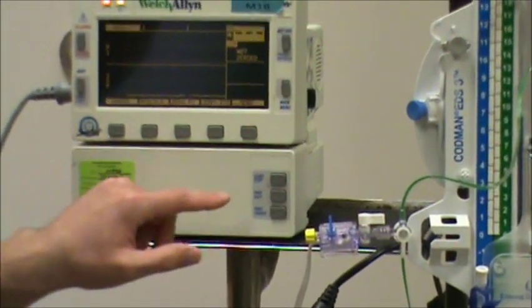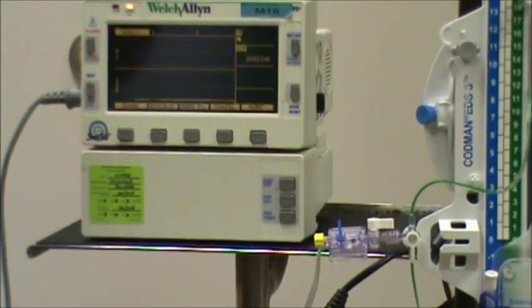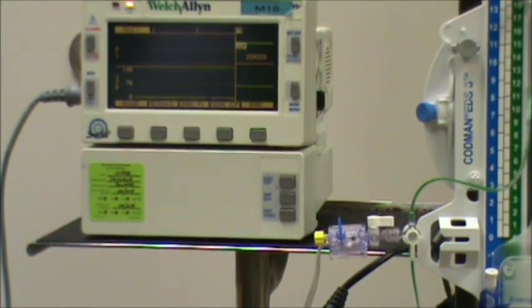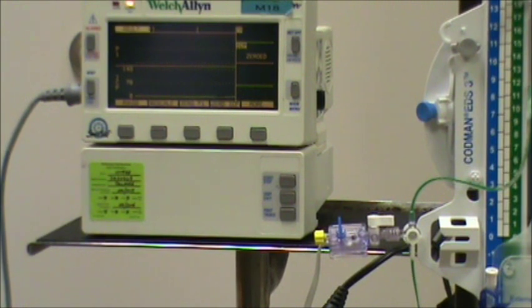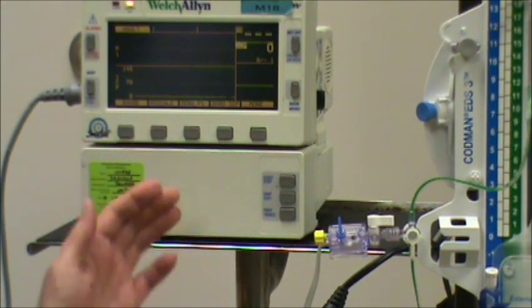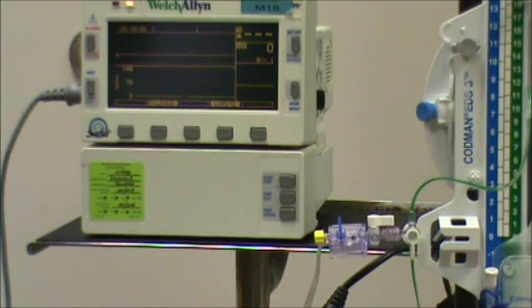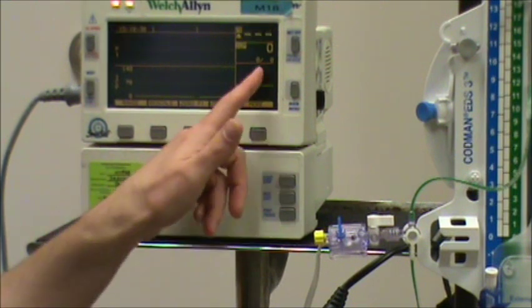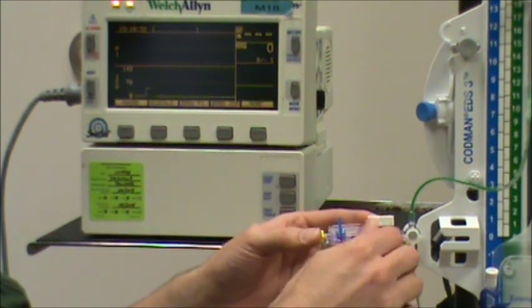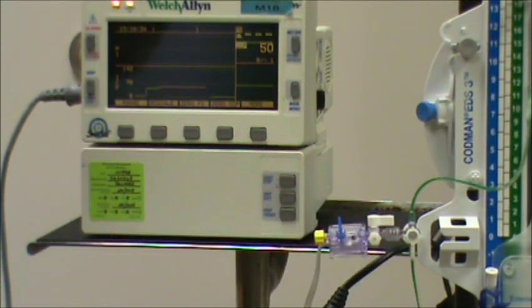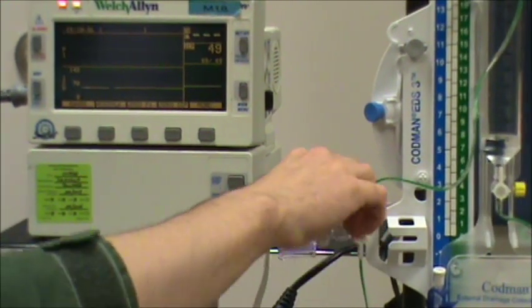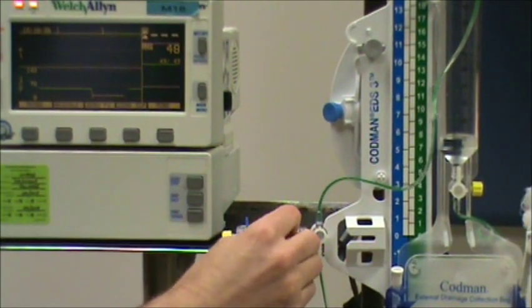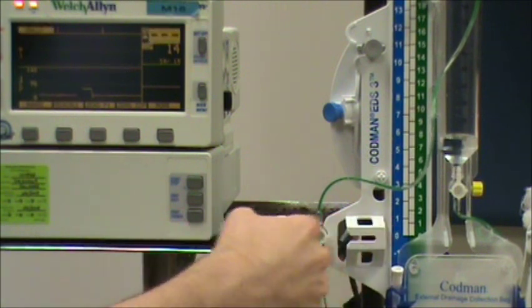So taking the cap off, we're going to hit 0 ICP, and it's going to say zeroing and then zeroed. If something's wrong in the system or it's done incorrectly, it'll give you 0 rejected. That way you just have to look back at your system, correct the issue, and then re-zero. So we also see zeros for the ICP, which means we've zeroed it correctly. And we need to turn the stopcock off to the cap so that it's open to the system.